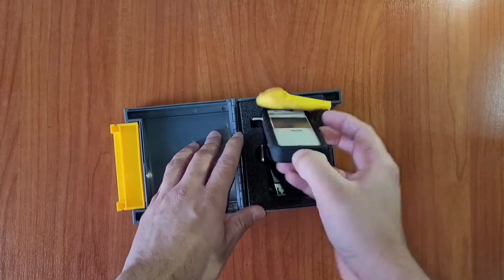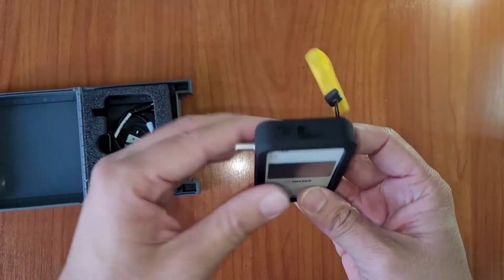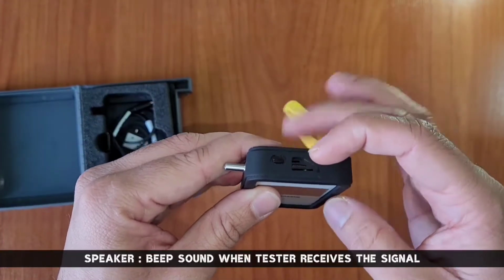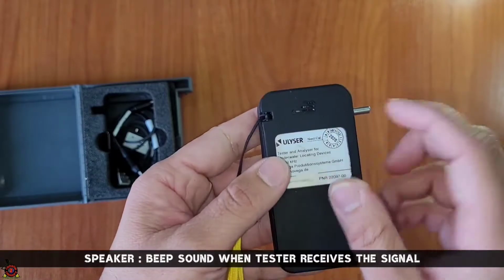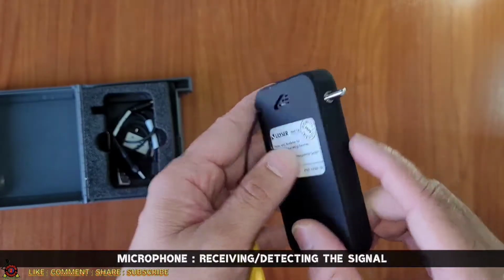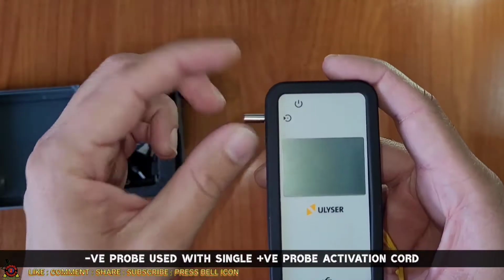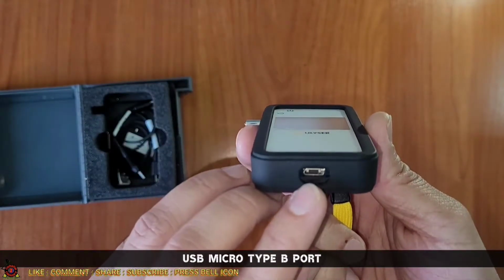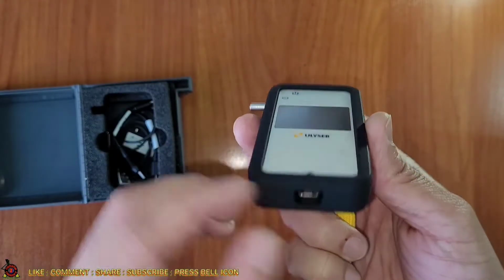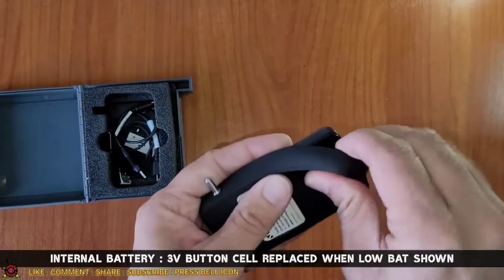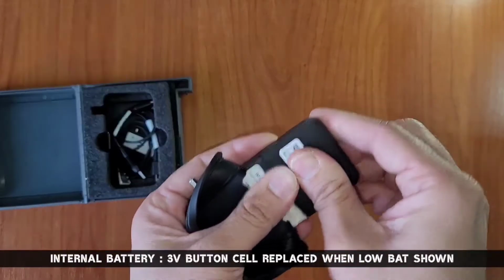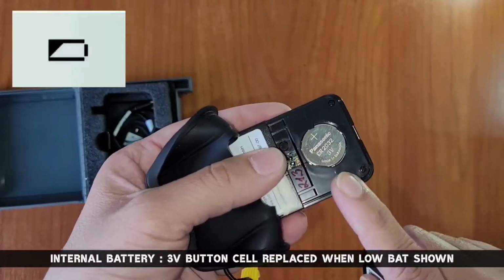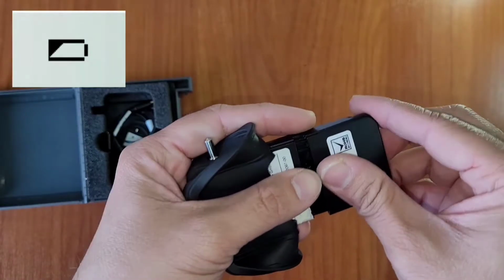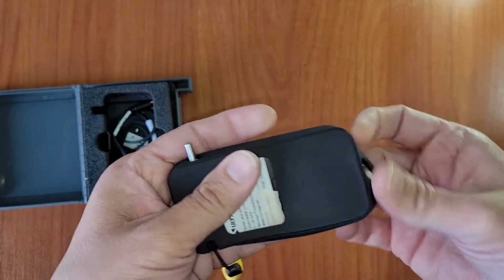So what we have here is the pocket size tester. It has got an on-off switch, the speaker from where we can hear the beep for receiving the signal, the microphone for detecting the signal. This is the probe, I'll show you the usage later, and the USB micro B type port. It has got an internal battery which has to be replaced once you get the low battery symbol. This is the 3 volt button type cell and the cover for protection.